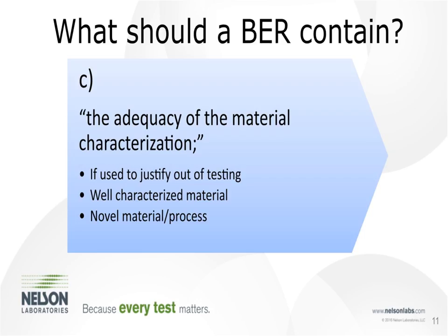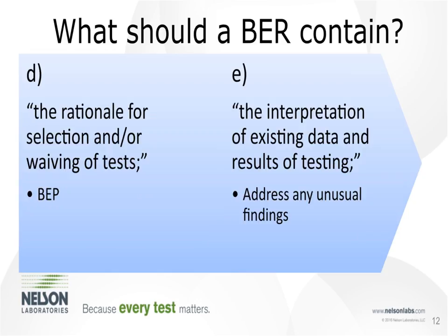And then another case is if you have a novel material or a new process, then there is a far heavier burden that is carried with this. So the agencies are looking for more material characterization data simply because there won't be enough information in the literature for us to research. So that will need to be provided and performed through your company on your device.